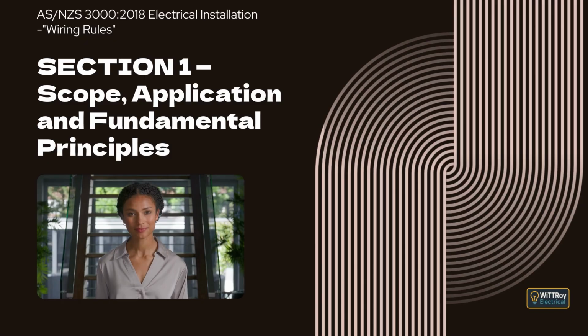Clause 1.1 is the scope. This standard sets out the requirements for the design, construction, and verification of electrical installations. It also covers the selection and installation of electrical equipment that forms part of an electrical installation. These requirements are here to protect people, animals, and property from electric shock, fire hazards, and physical injury. They apply when the installation is used with reasonable care and used for the purpose it was designed for. The standard also gives guidance so the installation works properly for its intended purpose, and so it can handle foreseeable issues such as temporary loss of supply.